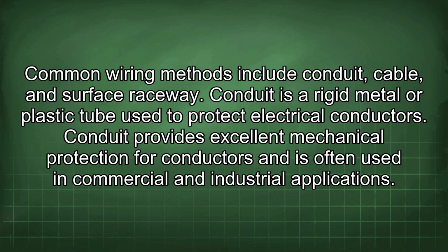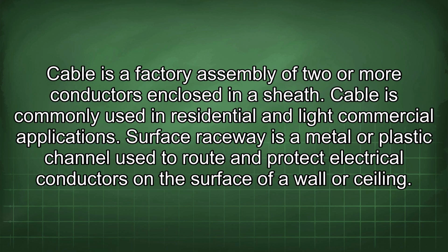Conduit is a rigid metal or plastic tube used to protect electrical conductors. Conduit provides excellent mechanical protection for conductors and is often used in commercial and industrial applications. Cable is a factory assembly of two or more conductors enclosed in a sheath. Cable is commonly used in residential and light commercial applications.